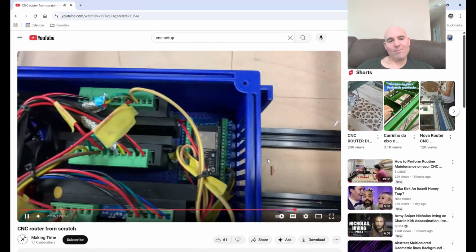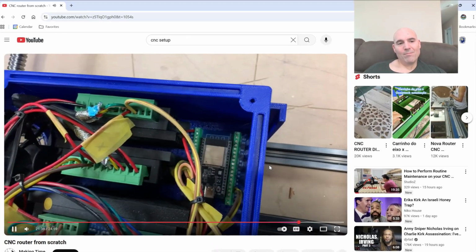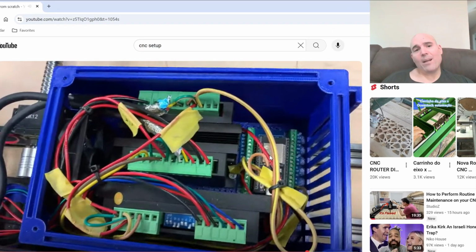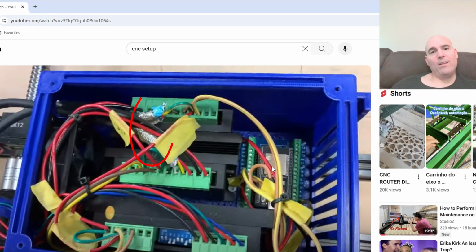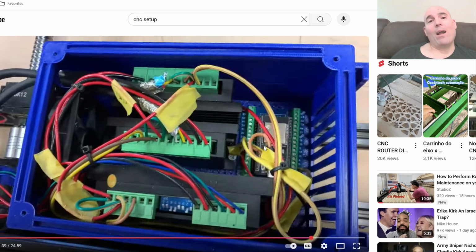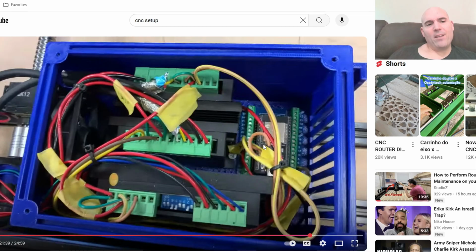Here's what everything looked like, screwed down and tucked away inside the box. Do I really need to say anything? I mean, we have shields that are completely exposed. Nothing is grounded because it's not possible. You have plastic and wood. Wonderful insulators. Not only that, you have a fire hazard. But that's okay. We'll let them continue.